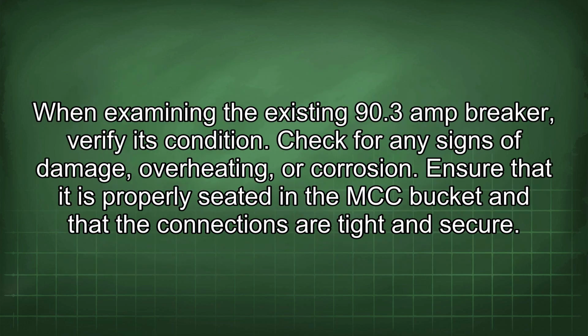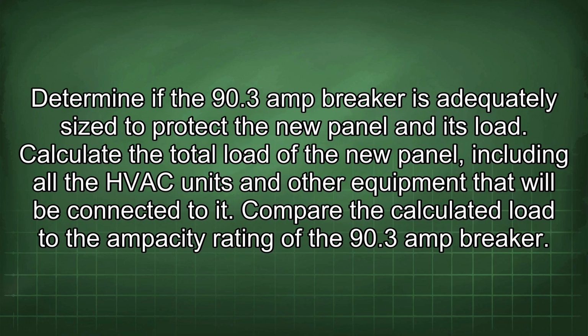When examining the existing 90.3 amp breaker, verify its condition. Check for any signs of damage, overheating, or corrosion. Ensure that it is properly seated in the MCC bucket and that the connections are tight and secure. Determine if the 90.3 amp breaker is adequately sized to protect the new panel and its load.